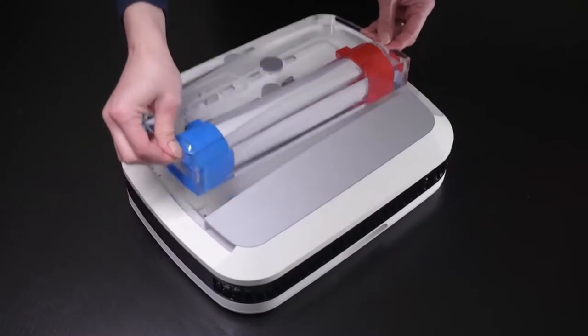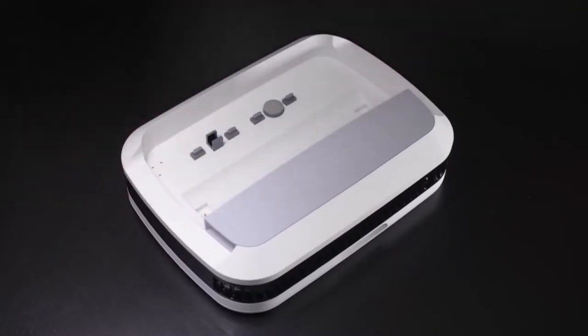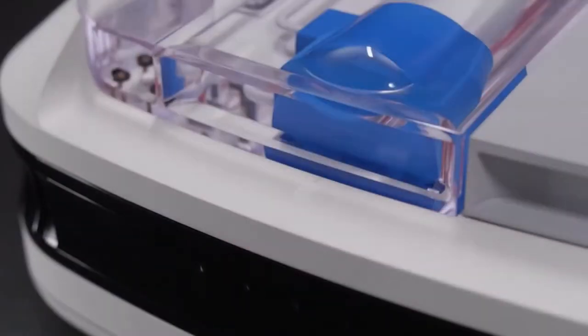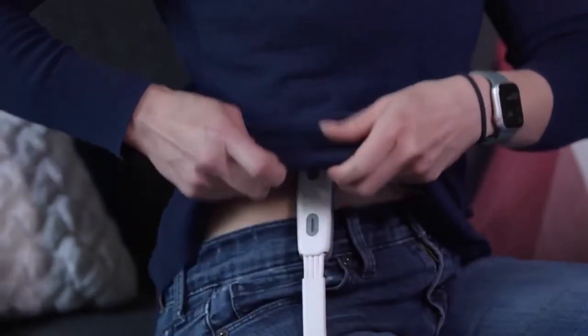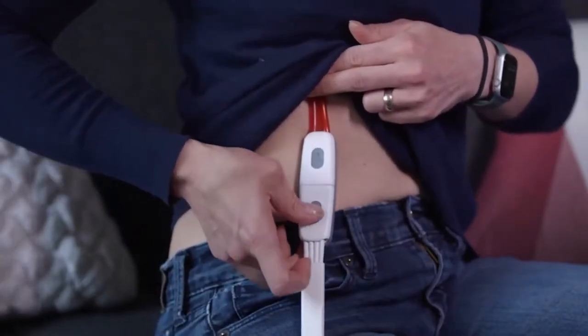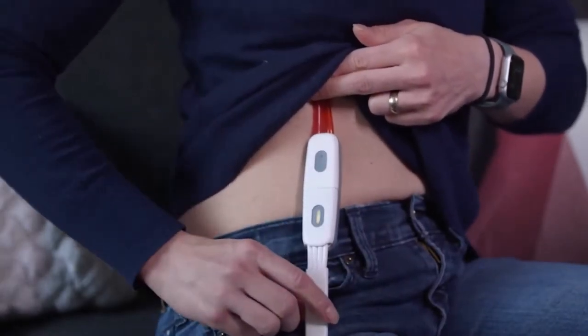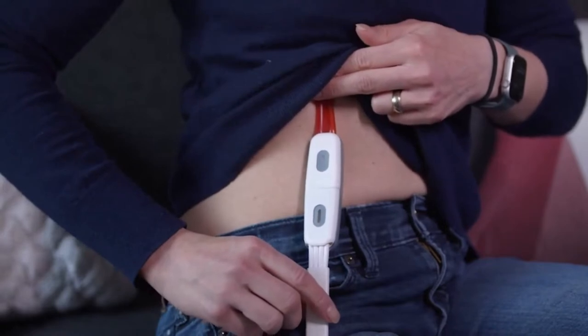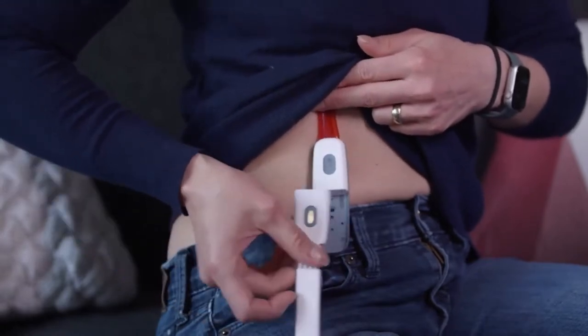Setting up the device is radically simplified by the Active's disposable blood management cartridge, and the extended life of the cartridge reduces the amount of monthly disposables. Connecting to and from the Active is made safe and easy with CDI's proprietary connection technology, designed specifically for wearable dialysis. No repeat needle sticks.